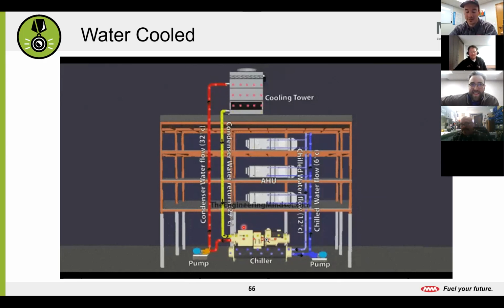Yeah, so here's a pretty good graphic of just exactly how a water-cooled chiller works. You can see on one side right here, we have our hotter water returning to the chiller. We are absorbing heat from that water into the refrigerant, leaving the water cooler as it leaves. And then you have that cool water delivered to the air handlers. And then on the condenser side of this, where we're taking that heat that we absorb from the water, we're going to send that hot water up to a cooling tower where it's going to go through. And there are a couple different types of cooling towers we'll go through. But basically, that hot water goes up to the cooling tower where we reject the heat outside. And then we return that water to where it can pick up more heat and keep repeating the cycle. We're just moving heat.